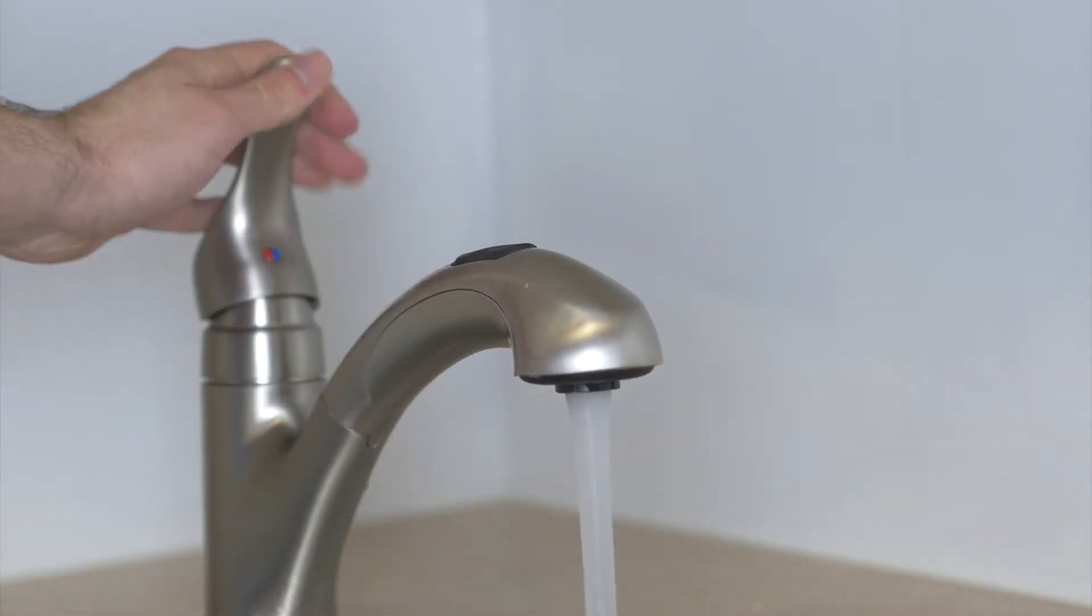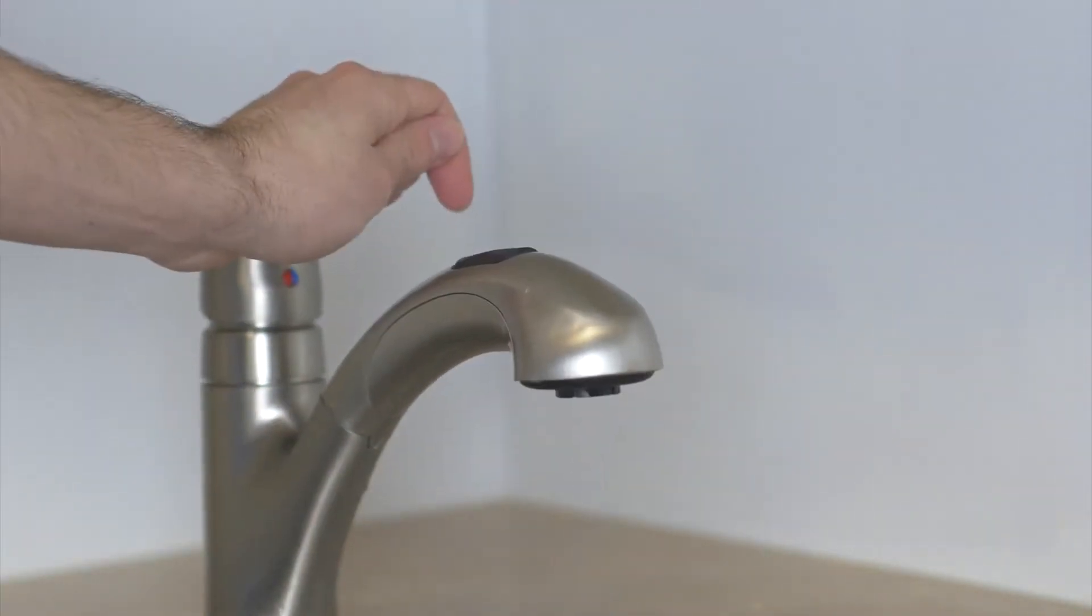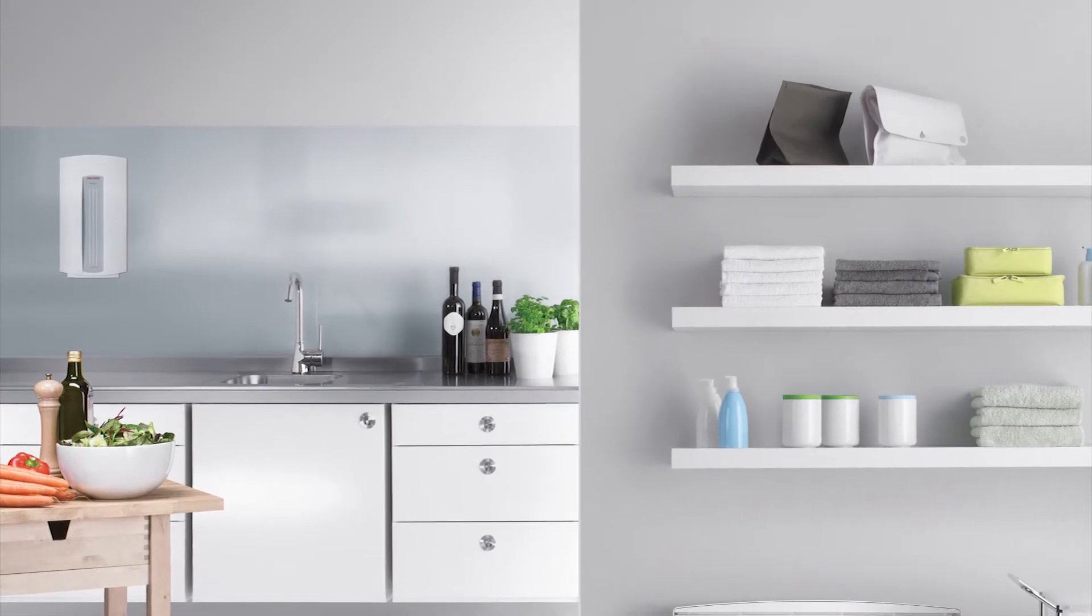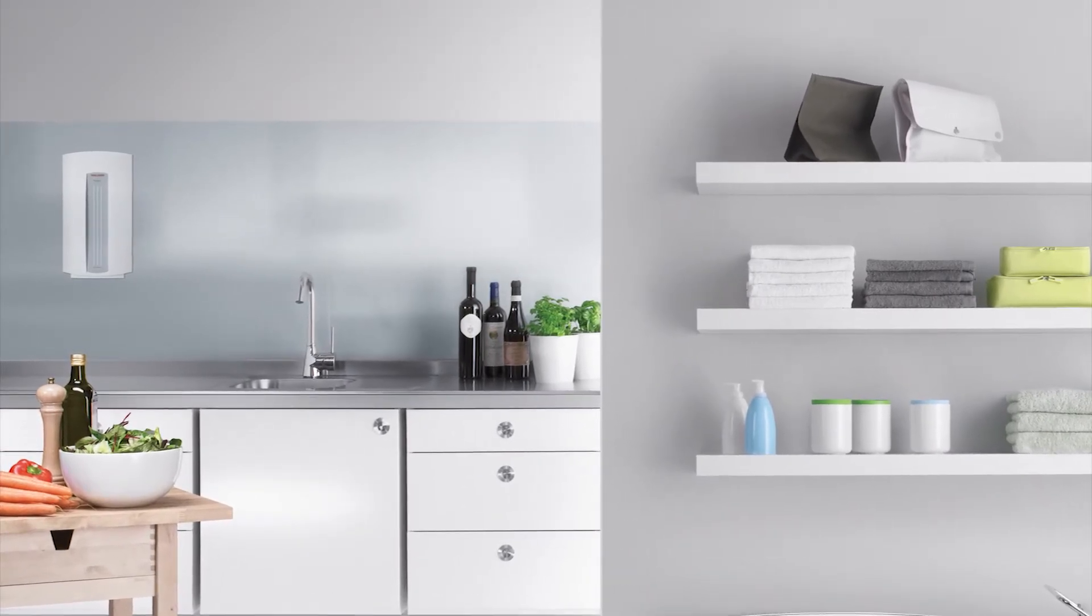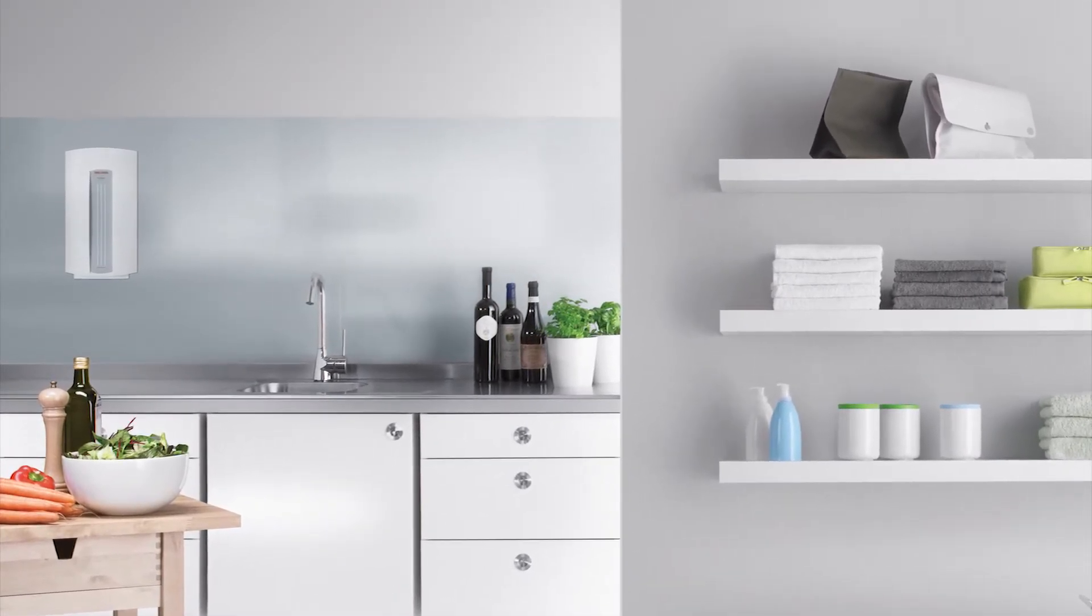And kitchen sinks dispense even more water. The standard flow rates for a kitchen sink vary from 1.5 to 2.2 gallons per minute. And since hotter water is often required at a kitchen sink, our largest point-of-use tankless water heaters are usually required to supply hot water.